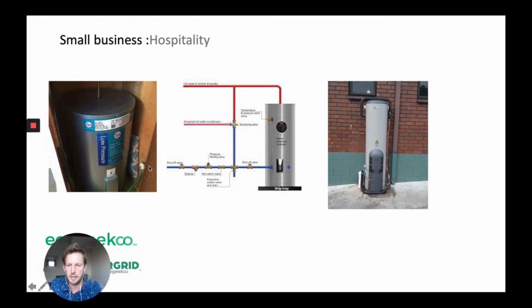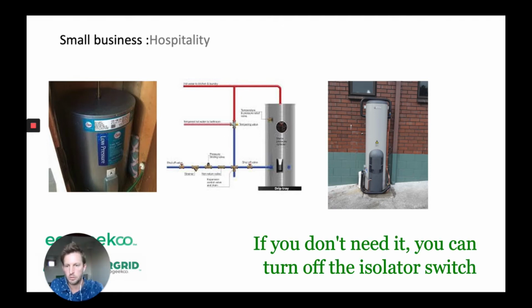But the key thing here is if you're sure that you don't need any hot water, it's not going to be used within the hotel room, you might have a chain of these hot water cylinders throughout your facility. They can account for about 35% of your energy baseload, so it's quite a lot of money being spent continually keeping water at 70 degrees, which is quite high. So quite simple, if you don't need them, you're going to be unoccupied for a while, you can just switch the isolator switch off at your cylinder.